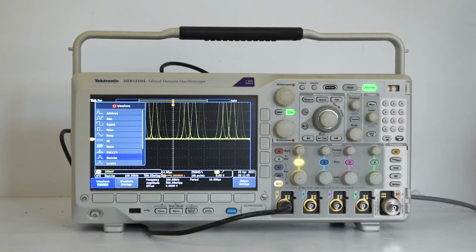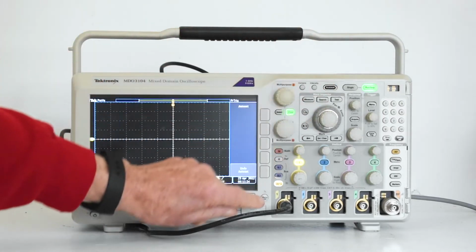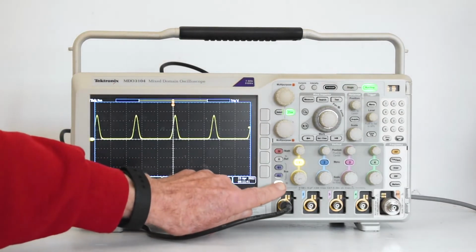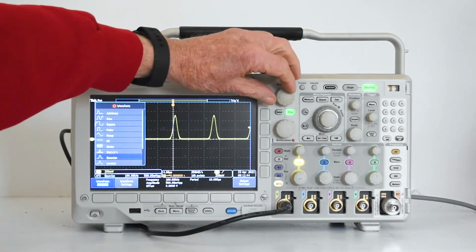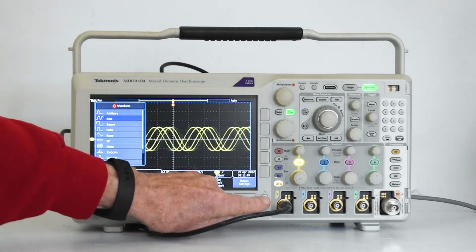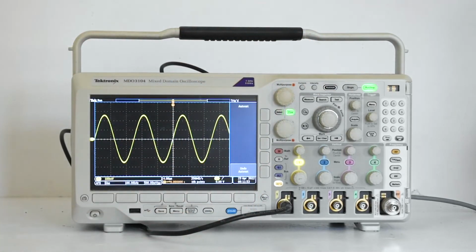In a previous time, the technician had to adjust frequency, amplitude, phase, and scaling, etc., until all of them came together correctly and simultaneously to get a cogent display. Now we just press Auto Set, and there it is. That is a stable Gaussian waveform. Going back to sine, we may have to press Auto Set again. Auto Set always sets the correct parameters for the waveform currently displayed.